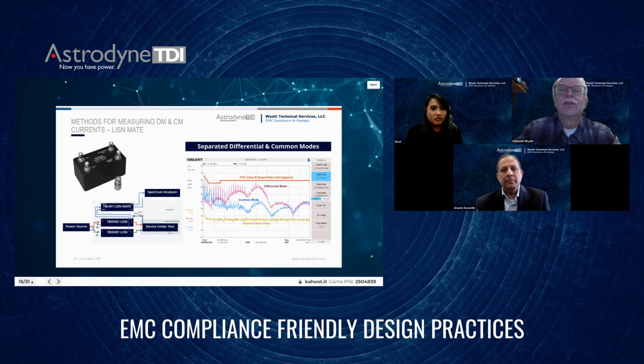As you can see on the screen capture on the right, the differential mode noise current is highest. So we need to ensure that whatever filter we select has high differential mode attenuation in that frequency range, roughly 10 kilohertz to 15 megahertz. You can look at the various attenuation curves, and that will help you select the appropriate filter for this particular noise you're measuring.